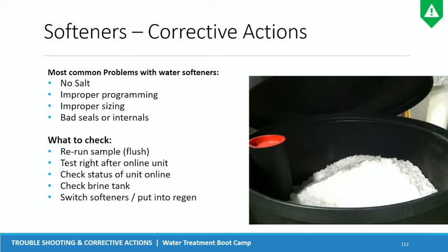Check your brine tank. Again, do you have salt? Did the salt bridge? So I always like to recommend to people, you should have some type of rod or something that weekly you're sticking in your brine tank to make sure you didn't have any bridging occurring. Salt can bridge, and then you don't actually have any salt in the water below it, but you think the tank is full of salt because it looks like it's full of salt. And then one thing you can always do is put a softener in manual regen, maybe a fluke, it just had a bad regen, and put the other softener online and then validate that that one's working properly.